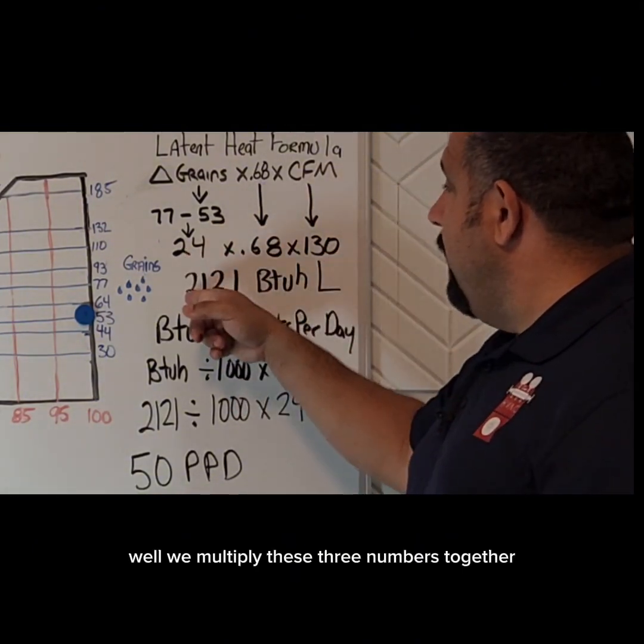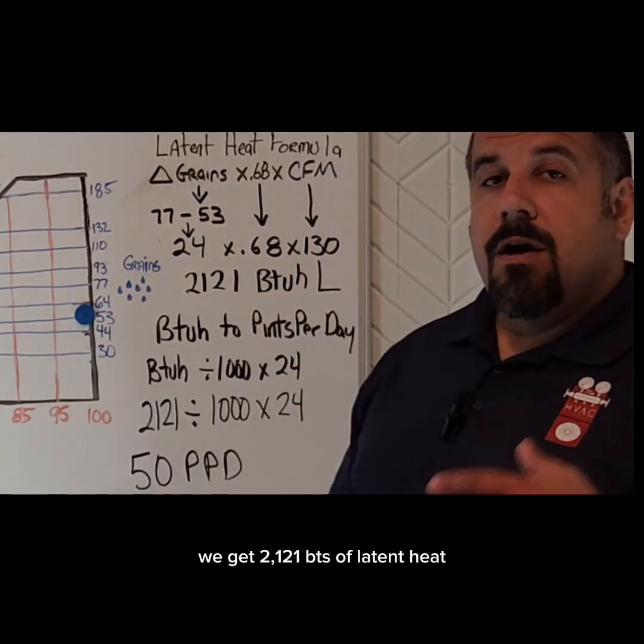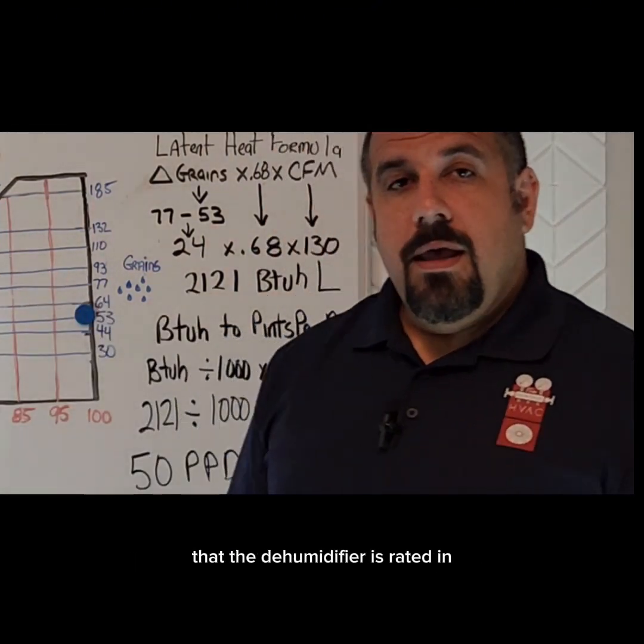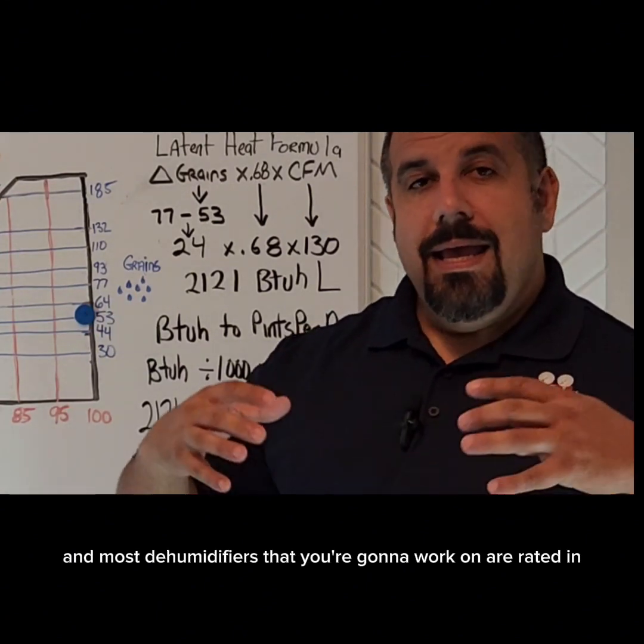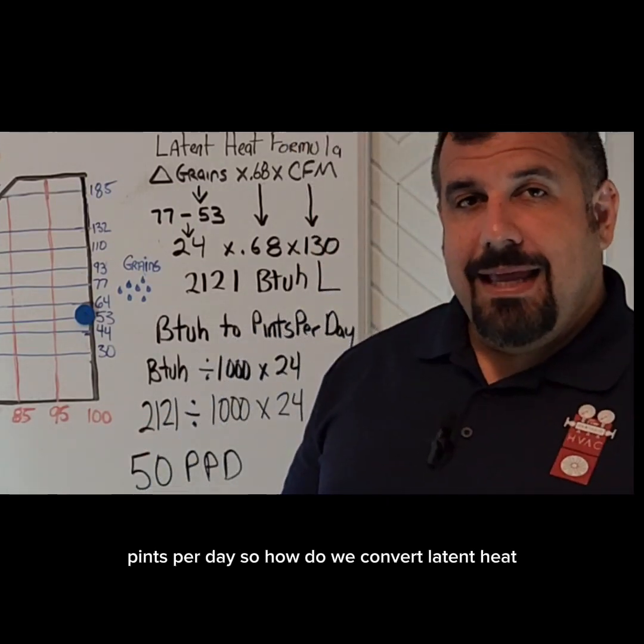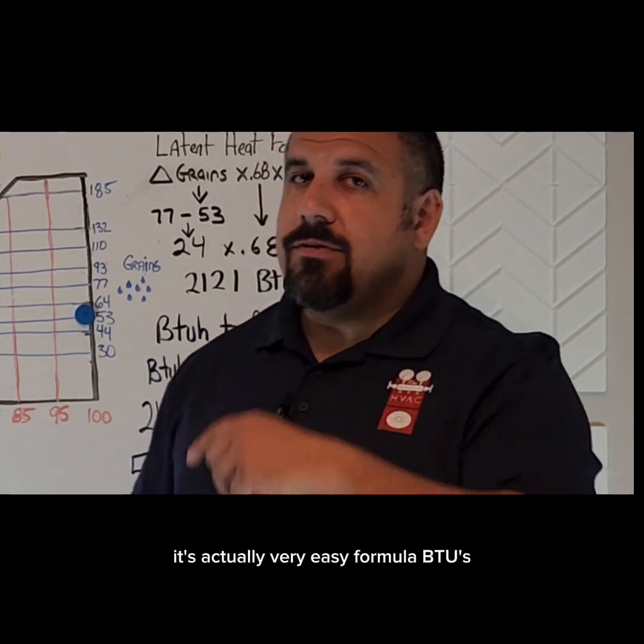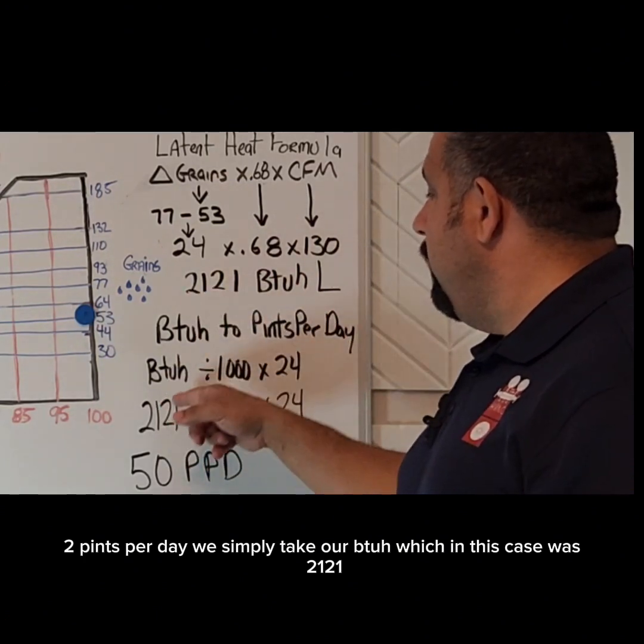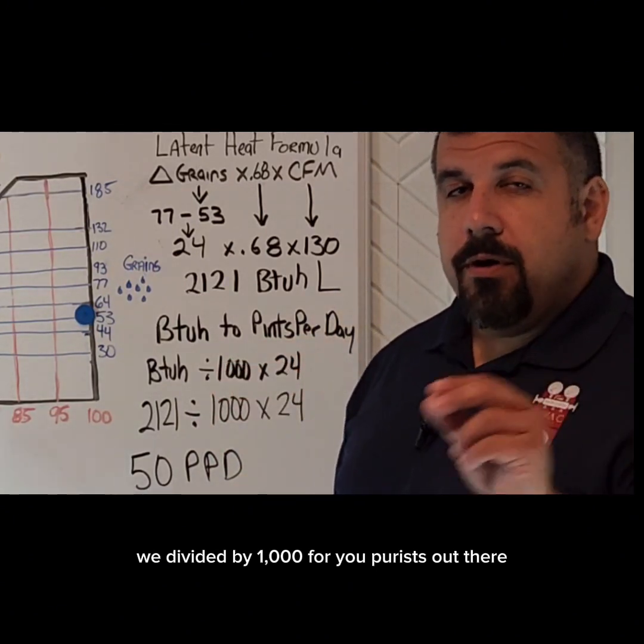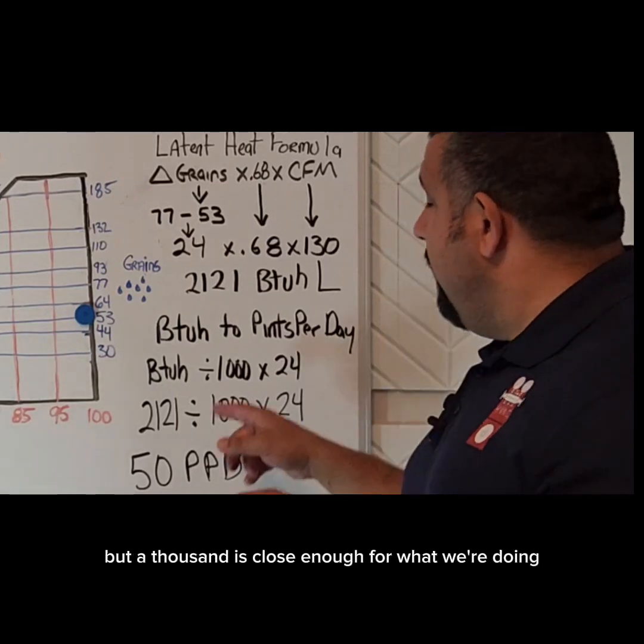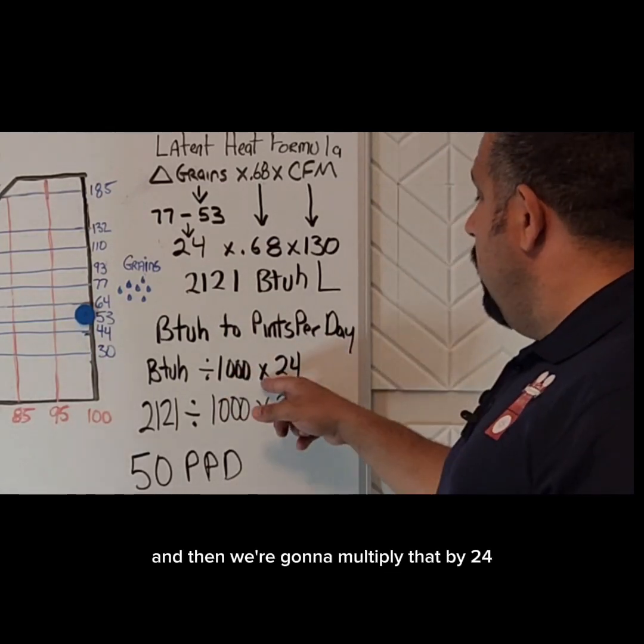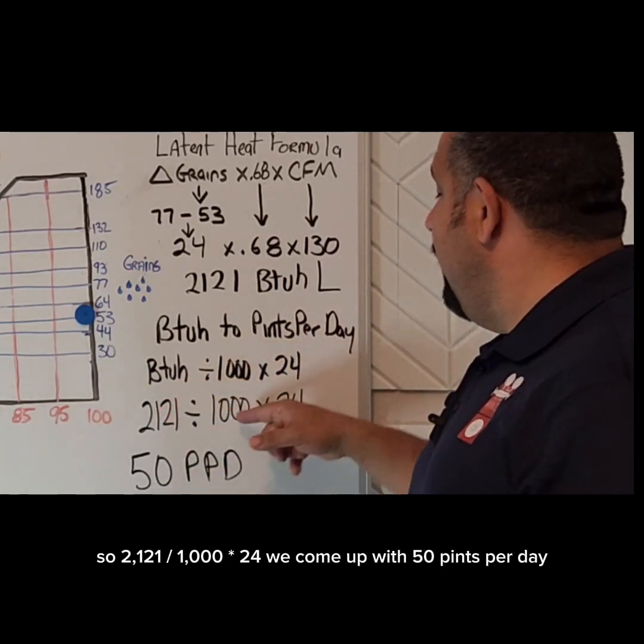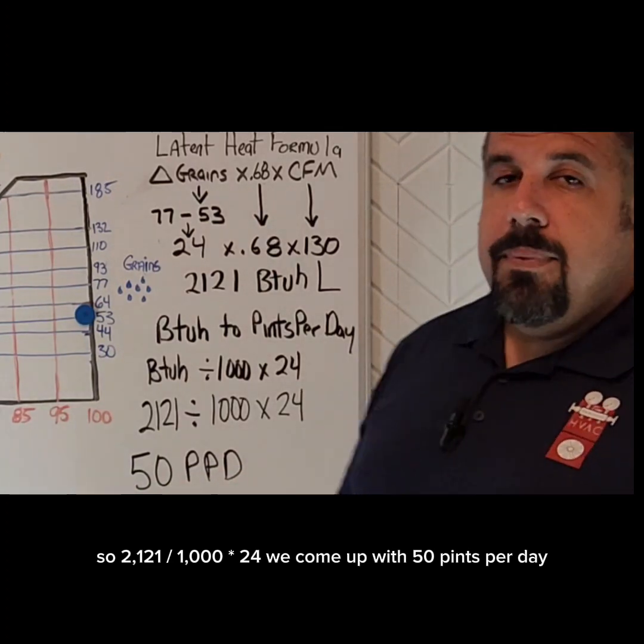When we multiply those three numbers together, we get 2,121 BTUs of latent heat. That does not do us a lot of good unless we're able to convert that to something the dehumidifier is rated in. Most dehumidifiers you're going to work on are rated in pints per day. To convert latent BTUs to pints per day, we simply take our BTUH — which in this case was 2,121 — divide it by 1,000 (for purists it's around 1,054, but 1,000 is close enough), and multiply by 24 because there are 24 hours in a day. So 2,121 divided by 1,000 times 24 gives us 50 pints per day.